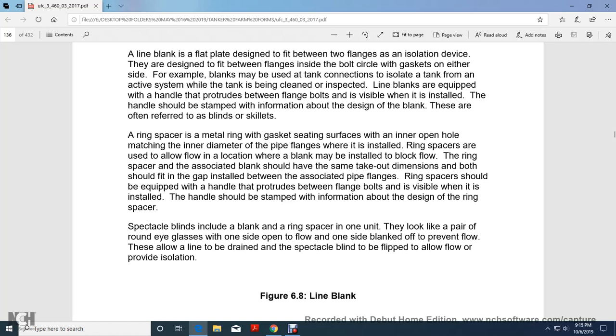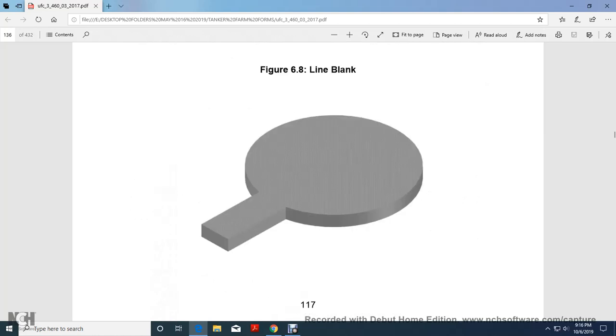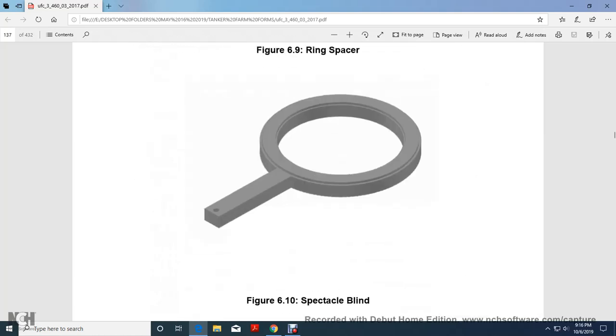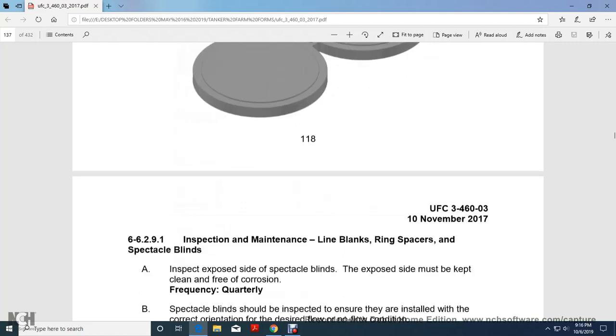The spectacle blinds include a blank and a ring spacer in one unit, and they look like a pair of round eyeglasses. One side is open to the flow and one side is blanked off to prevent flow. These allow the line to be blinded, drained, and the spectacle blind to be lifted to provide isolation. This shows a line blank, a ring spacer, and a spectacle blind.